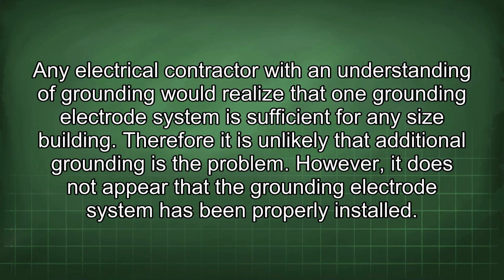Any electrical contractor with an understanding of grounding would realize that one grounding electrode system is sufficient for any size building. Therefore, it is unlikely that additional grounding is the problem. However, it does not appear that the grounding electrode system has been properly installed.